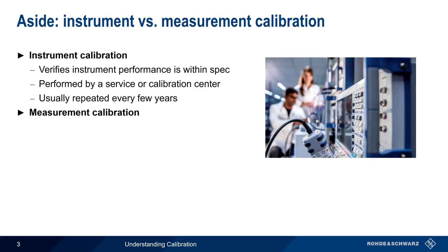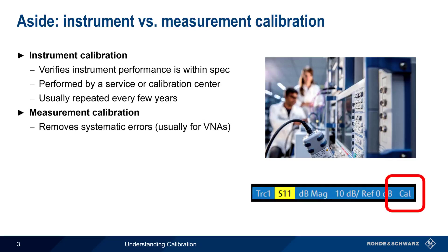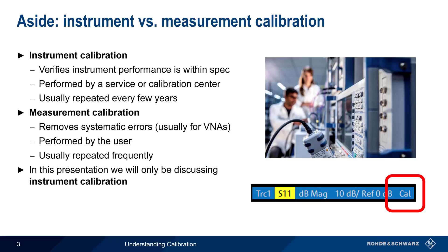A measurement calibration, on the other hand, is performed to remove systematic errors from a test setup, most often when making measurements with vector network analyzers or VNAs. It's always performed by the user and is repeated rather frequently — often before each measurement session, or at least before important measurements. In this presentation, we'll only be covering instrument calibration, so please see the separate presentation on VNA measurement calibration if you'd like to learn more.